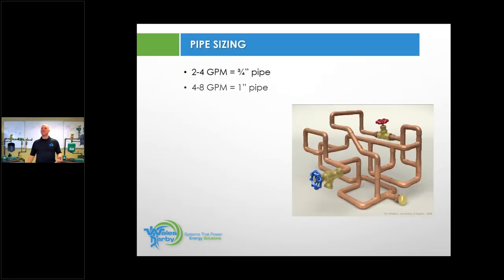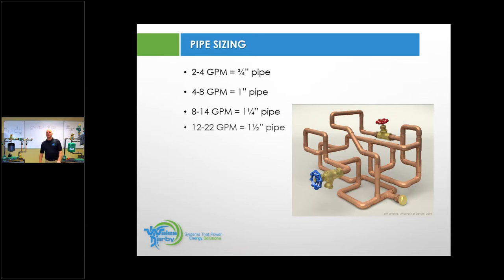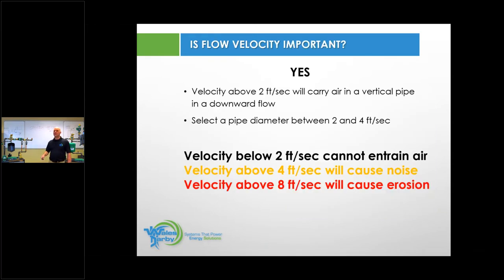This is just to confirm some of the flow rates. Again, if you want to take a quick snapshot of that, that'll keep you within that 2 to 4 feet per second on your flow and velocity. Okay, keep us away from having noise. There's the velocity again, 2 to 4 feet per second. Once we get above 4, we get to 6, noise. We get to 8, erosion.